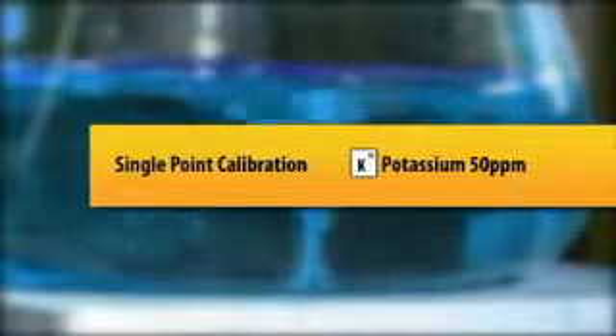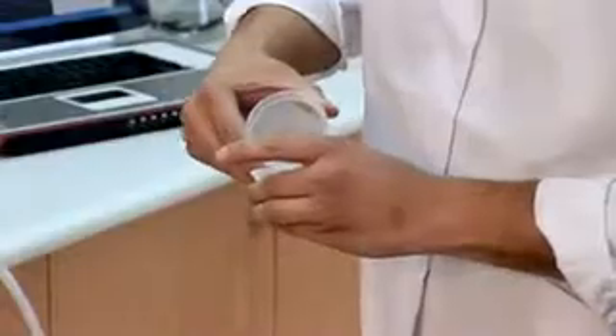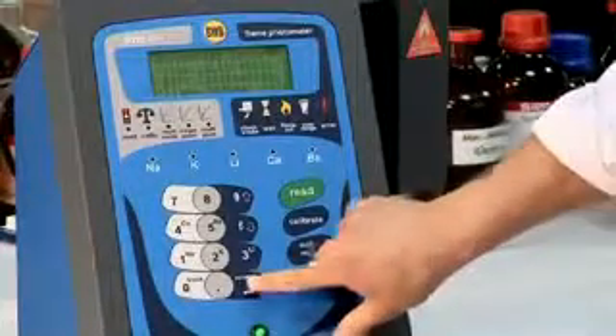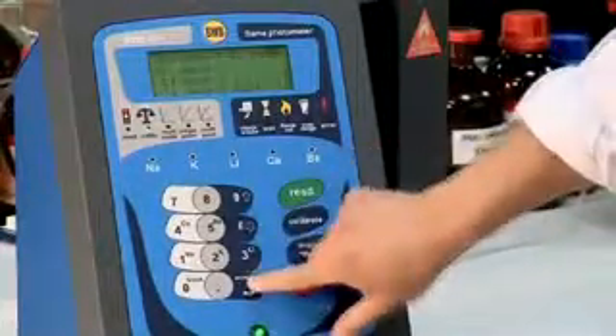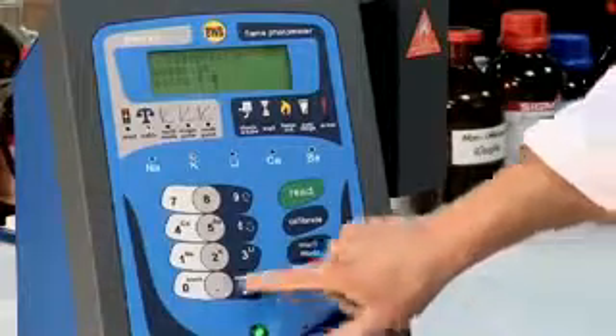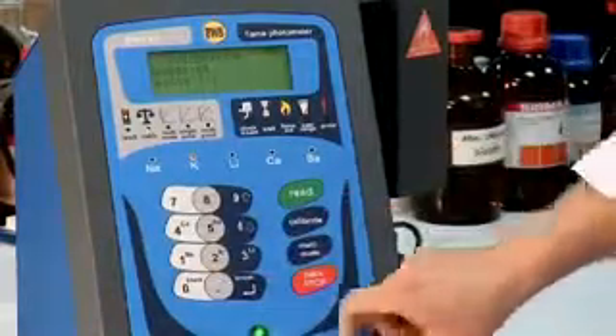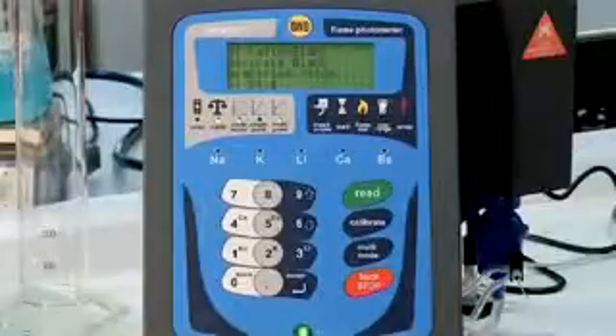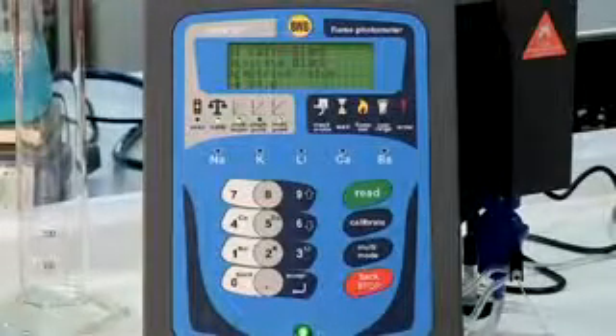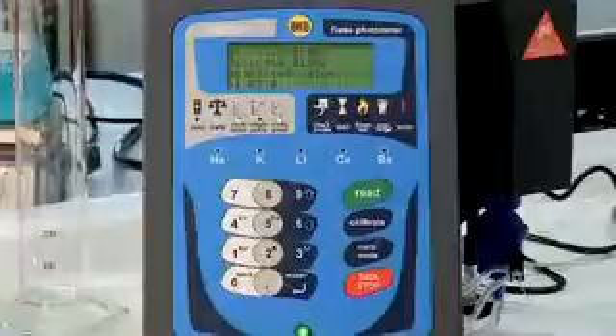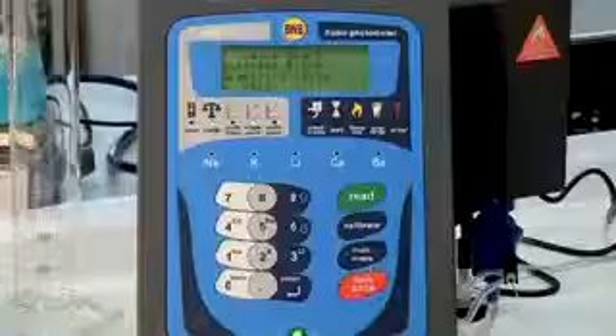Now that the Bwb Xp is set up and ready to go, the next step is to calibrate the instrument. Before we start our calibration, we can set the units in which we want to calibrate and display. The Bwb Xp can be set to parts per million, milligrams per litre, milliequivalents per litre, and millimoles per litre. There is an additional units option for those who wish to use a different method of measurement. For our example, we will choose parts per million.